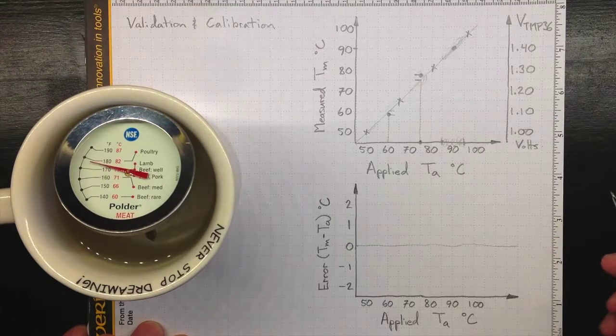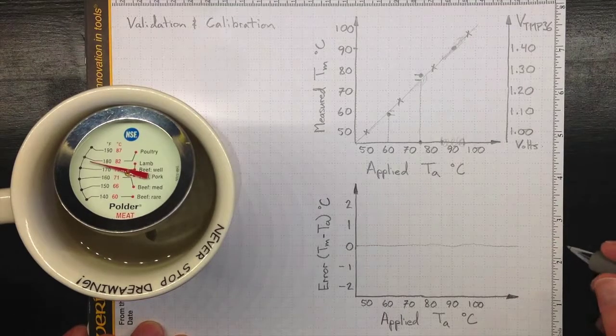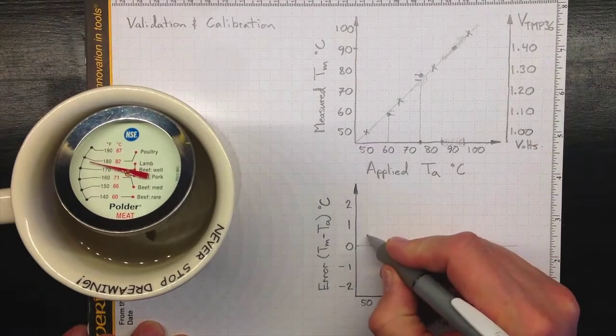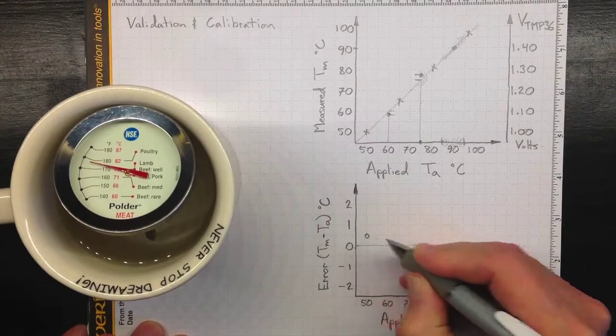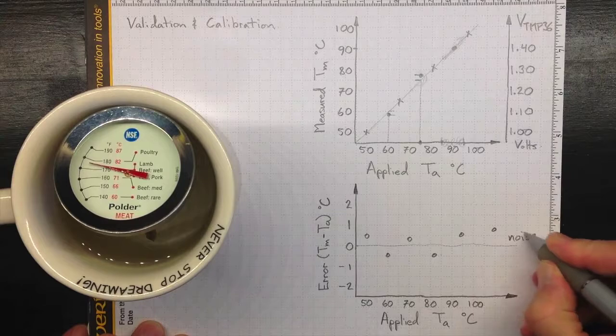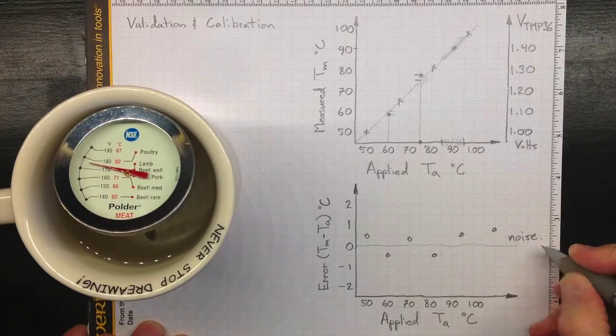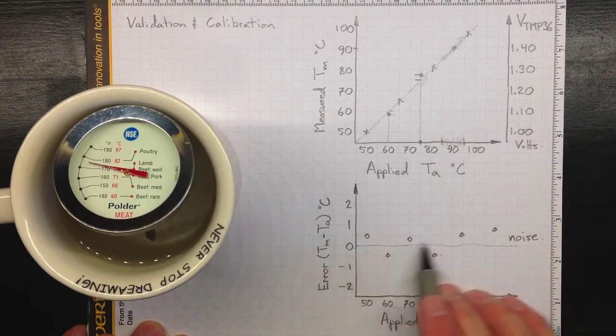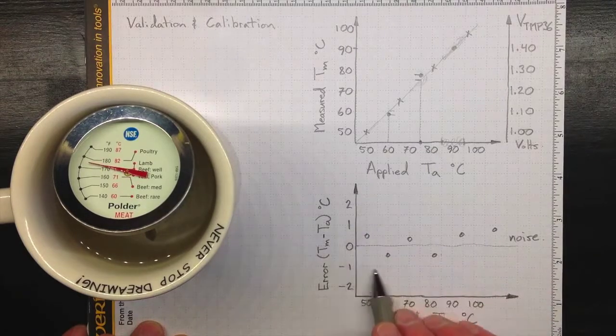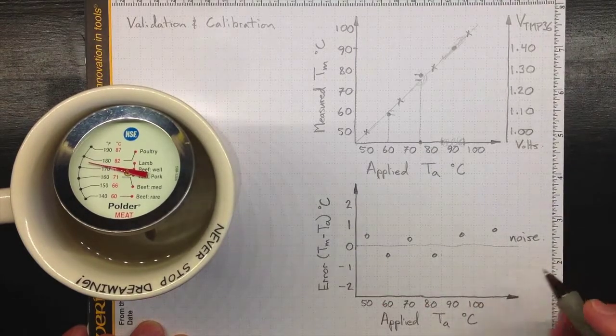However, our measurement isn't going to be perfect. Inevitably, there's going to be some noise. We might actually find that our data points look something like this. This tells us that our calibration, our instrumentation is pretty good, but we've got some noise, and all of our data points are still within plus or minus one degree Celsius. That's pretty good.